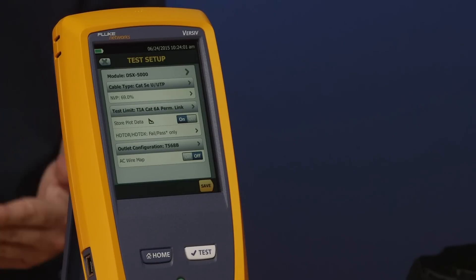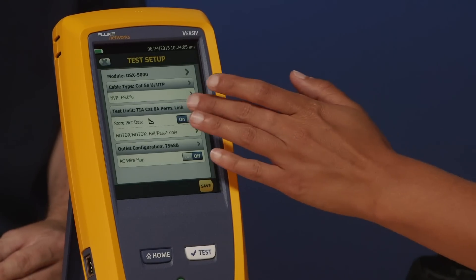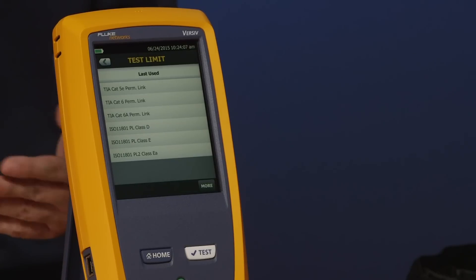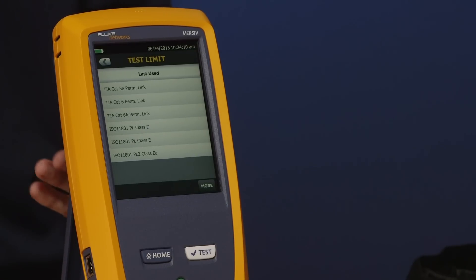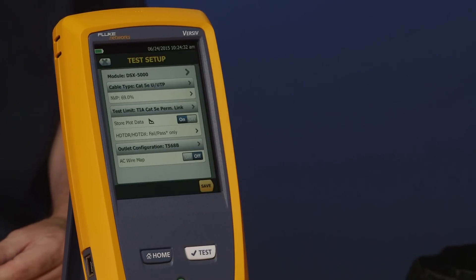The most important thing is our test limit. Go ahead and tap test limit. Just like cable type, it shows the last-used list. On this new instrument, we've put up the six most common test limits: the three TIA standards and three most common ISO standards, mainly permanent link since most testing is done for warranty applications. Go ahead and select TIA Cat5e permanent link.